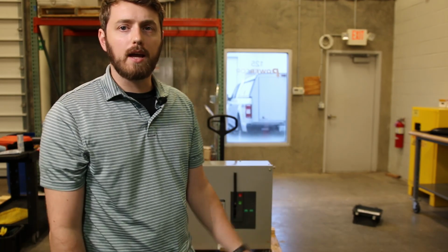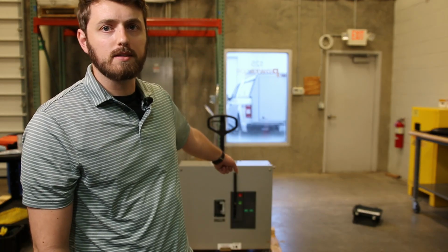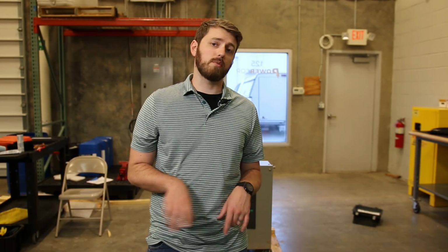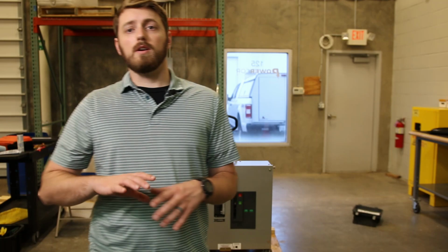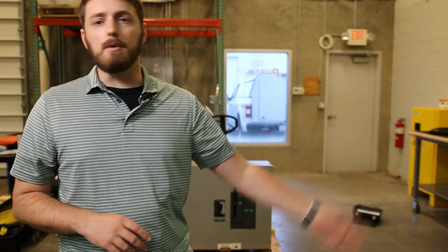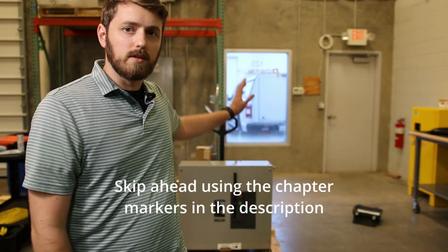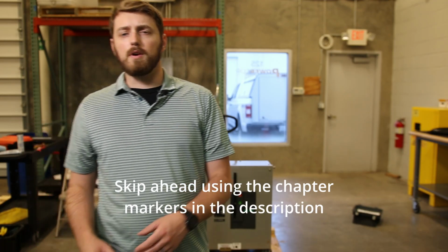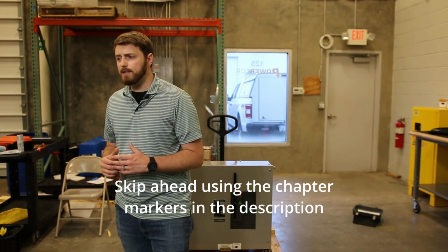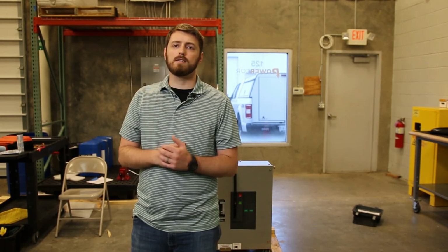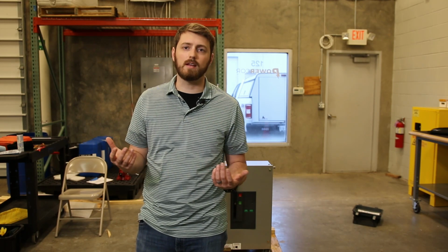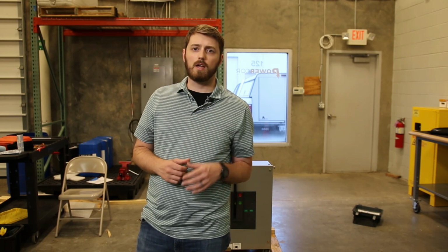Today we're going to take a look at how we test one of these guys. This is a 5 kV medium voltage vacuum circuit breaker. Every breaker is a little bit different. The Eaton's different than the ABB's, different than the Square D's, different than the Siemens. But for the most part, the steps that we take to test them are going to be pretty much identical, with a few little caveats here and there.